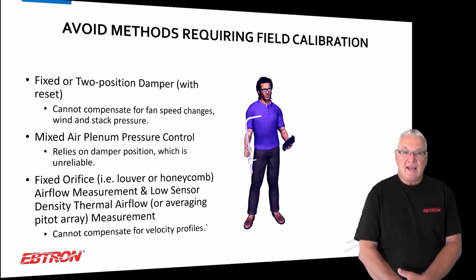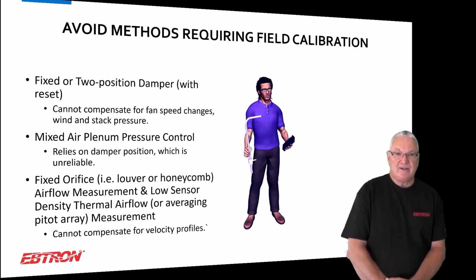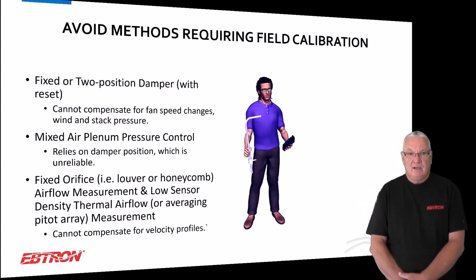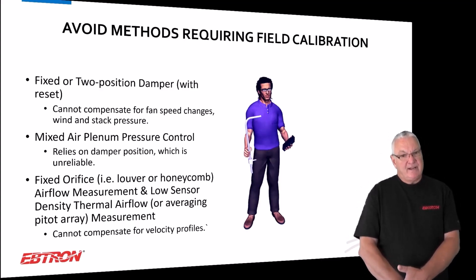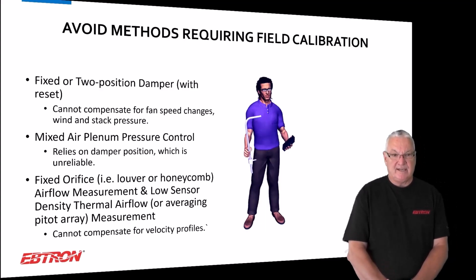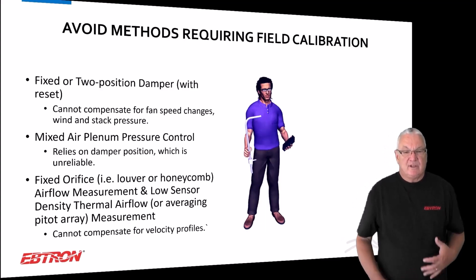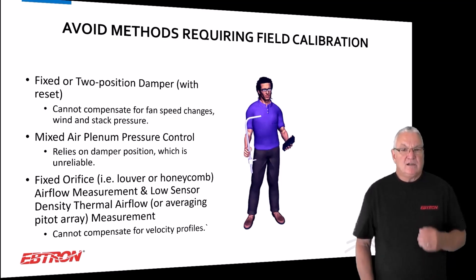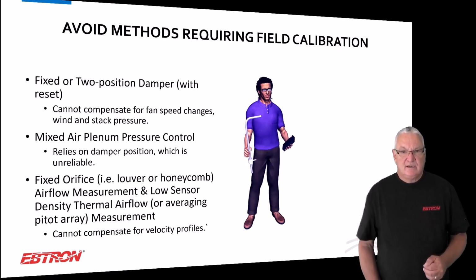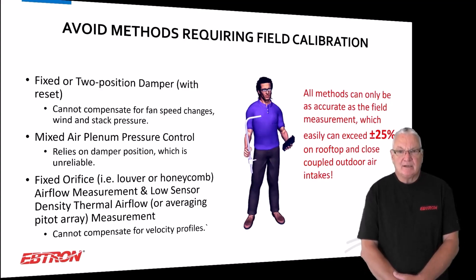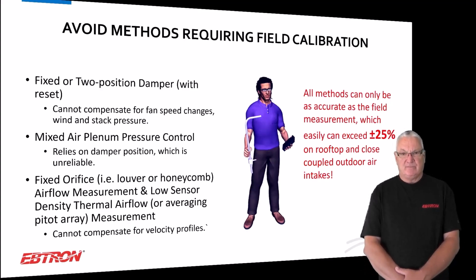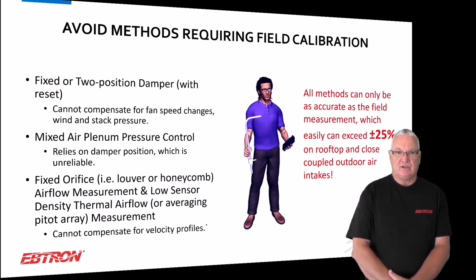So you have to be really careful with that strategy, as you do if you put in a very low sensor density, like one or two sensors on a big intake. I don't think it's a great idea for control. So you have velocity profile problems. Regardless, on all of these methods, it cannot be any better than the field measurement, because they all have to be field calibrated. You don't know the flow coefficient of the louver.